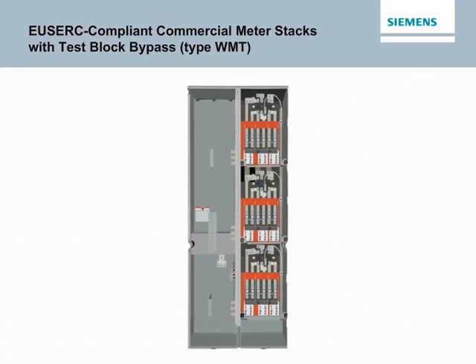EUSERC-compliant commercial meter stacks with test block bypasses, type WMT, are available with single phase and 3-phase tenant main provisions. 225 amp single phase and 3-phase tenant main stacks are available up to 3 positions. Stacks with single phase 225 amp provisions can be converted to 125 amps without the need for costly labor-intensive conversion kits.